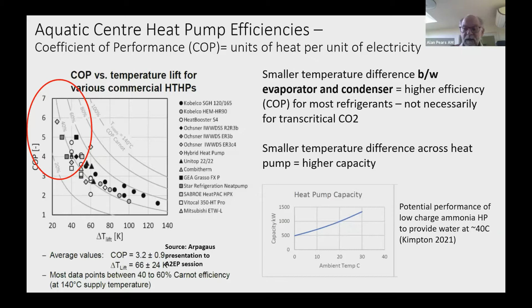So another key point is that what this graph is showing is the capacity of a heat pump when it's delivering heat at about 40 degrees. And as you can see, as the temperature gets closer to 40 degrees, which is the outlet temperature, the capacity of the heat pump increases as well. So what this means is that the heat pump can do more. The converse of all this is that if you're allowing a heat pump to run in a really cold environment and you're trying to heat the water up to a high temperature, you will need a much bigger, more expensive heat pump, and you'll save less energy. So these are the key messages from this. Now, we can address a lot of these issues by looking at the exhaust air.